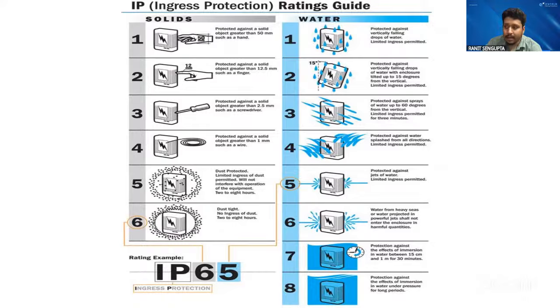After 30 minutes, they take it out of the water and check there's no water ingress. They check if the output is working - if the inverter works, if the battery pack output voltage is fine, if any short circuit happens, or any fire cases. For battery packs especially, if there's a short circuit or fire case, the battery will be rejected on the IP67 test.